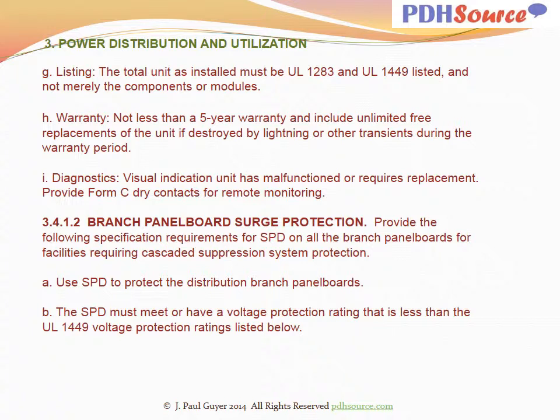With regard to branch panel board surge protection, provide the following specification requirements for surge protection devices on all the branch panel boards for facilities requiring cascaded suppression system protection. Use surge protection devices to protect the distribution branch panel boards. The SPD must meet or have a voltage protection rating that is less than the UL1449 voltage protection ratings listed below.